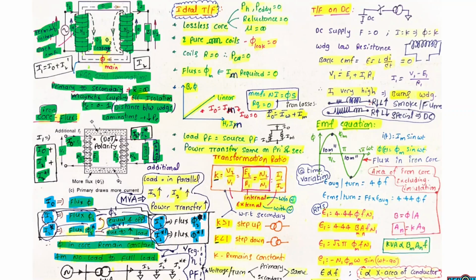This is the representation here. This is our transformer kVA, and on one side we have connected the supply voltage, on the other side we have connected the load. Say the load is equal to 50% of our transformer rating. Then it draws only I2 current. And we have increased the load and added 20% extra load. That means now the total load on the transformer is 70%. This second set of load will draw current I2 star. And we have added the remaining 30% of load. This 30% of load draws I2 double star.